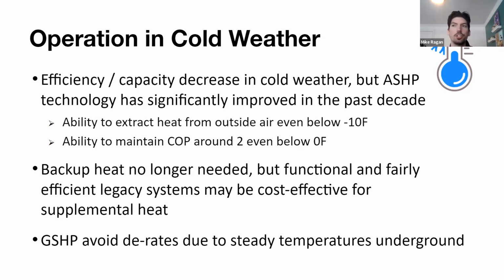That's a question where I would just challenge you to take a look at your utilities. What is the gas rate versus the electric rate? At that point, you could perform a cost-benefit analysis to see at what temperature those particular technologies would be more advantageous. Now, further, in cold weather, we no longer require backup heat for air source heat pump equipment. In previous generations, when our equipment lagged behind as temperatures approached 0 degrees, that's not the case anymore. We have VRF or heat pumps as a whole as the sole sources of heat for entire buildings.